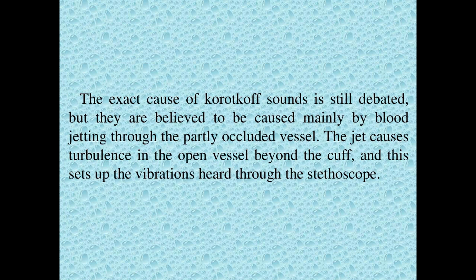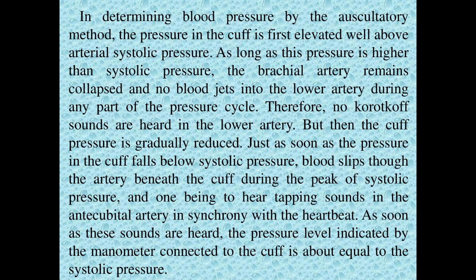The exact cause of Korotkoff sounds is still debated, but they are believed to be caused mainly by blood jetting through the partly occluded vessel. The jet causes turbulence in the open vessel beyond the cuff, and this sets up the vibrations heard through the stethoscope. In determining blood pressure by the auscultatory method, the pressure in the cuff is first elevated well above arterial systolic pressure. As long as this pressure is higher than systolic pressure, the brachial artery remains collapsed and no blood jets into the lower artery during any part of the pressure cycle.